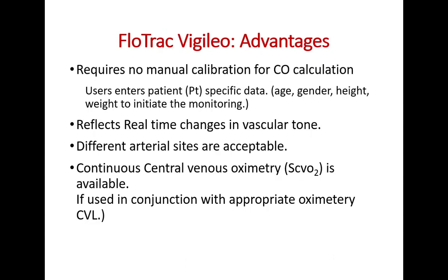Advantages obviously: no manual calibration is required. It reflects real-time change in vascular tone. Different arterial sites are acceptable. Continuous ScVO2 is available if it's used in conjunction with an appropriate oximetry-equipped central venous line. So that's separate, but continuous ScVO2 is available because there's a port in the Vigileo monitor for ScVO2 monitoring. So if your central line is equipped with continuous ScVO2 monitoring, you can always attach it to the Vigileo monitor. This is an add-on. It doesn't come as part and parcel of your FloTrac. It's a part of the monitor.